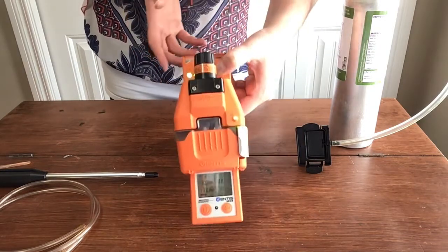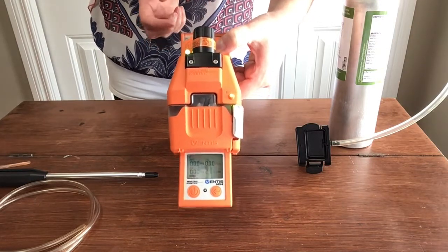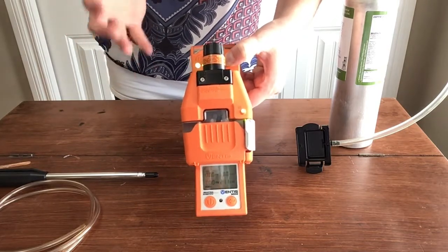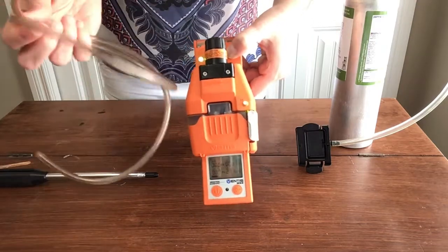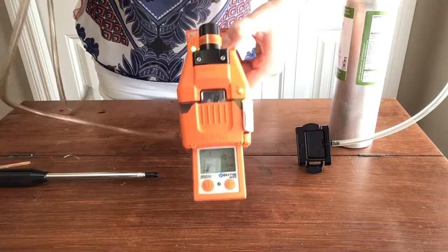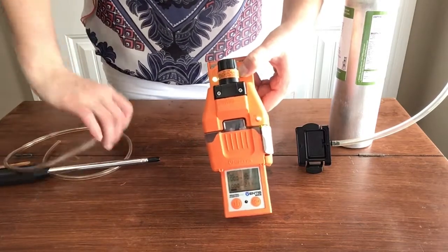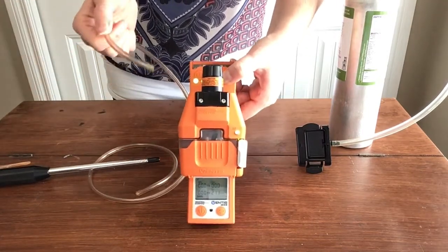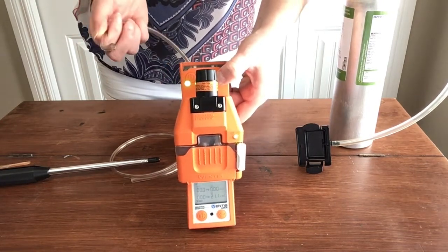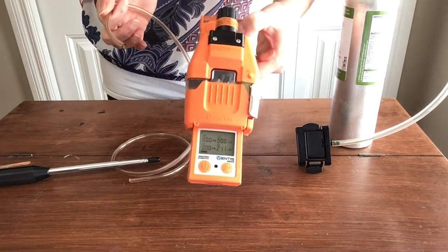Once it checks those, you can hear it is running. The last thing that you need to do before you take this out and use it for your confined space monitoring is you need to check and make sure that the safety system is working. And what I mean by that is if let's say you're using a tubing much longer than this, and you're dropping it into a confined space that goes down quite a distance, might be dark, you can't see. If the end of this tubing for some reason ended up in water or dirt or something of that nature where it's not actually drawing air from the confined space, we need to know about that because otherwise our readings look normal, but it's not actually pulling air.